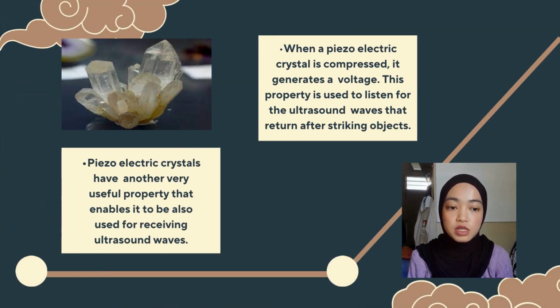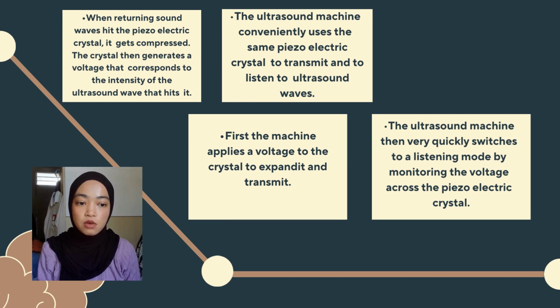I will continue to present about receiving ultrasound. Piezoelectric crystals have another very useful property that enables them to also be used for receiving ultrasound waves. When a piezoelectric crystal is compressed, it generates a voltage. This property is used to listen for the ultrasound waves that return after striking objects. When returning sound waves hit the piezoelectric crystal, it gets compressed. The crystal then generates a voltage that corresponds to the intensity of the ultrasound wave that hits it.